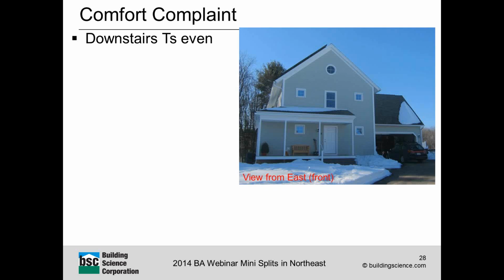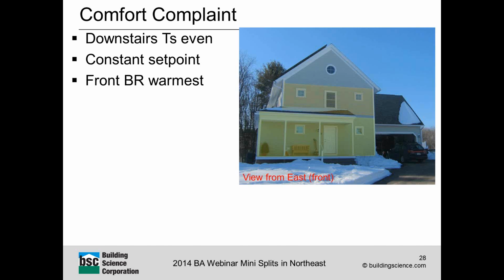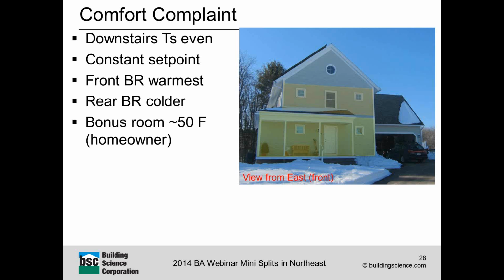The homeowner said the downstairs temperatures were pretty darn even, running a constant set point on both the first and second floor. There was a bedroom at the front of the house that was generally the warmest, with a few complaints there. The rear bedroom was colder than that, but the bonus room was actually very noticeably cold, 50 degrees in some of the really cold worst case conditions, with a 70 degree, 68 degree set point inside. That shows the footprint of the bonus room.